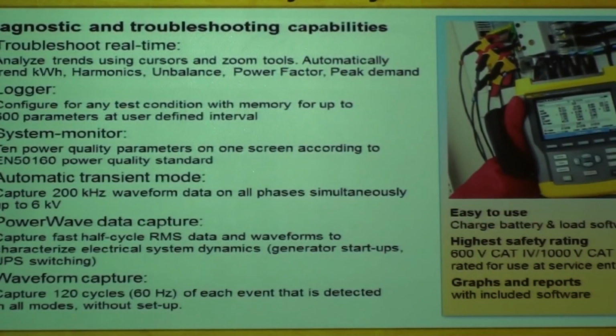So that's the 435 Power Quality Analyzer. This is an extended power quality tool that's used for diagnostic and troubleshooting work. It not only measures the power and energy, but it also helps you to troubleshoot your problems with harmonics, so you can troubleshoot in real time. It has a logger function. There is a system monitoring function that will tell you how clean the power is that you get from the utility. So if you want to understand if the power supply coming into my building is clean, I need to do system monitor. It has an automatic transient mode that will automatically capture any high voltage switching that you experience within your measuring period. It's got power wave data capture, ideal for large motor startups and generator startups, and waveform capture.